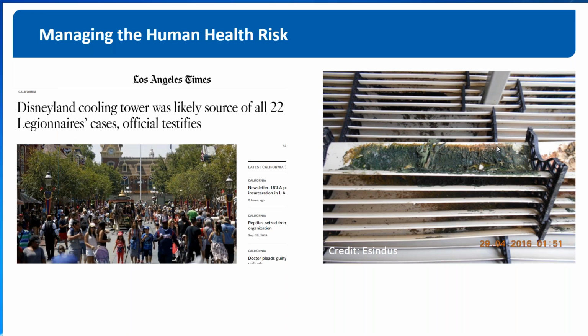Legionella bacteria grows in biofilm, which is a heat transfer inhibitor. So dispersants are normally used to keep process surfaces clean, and this process strips biofilm growth off the cooling tower structure. It's then fluidized as a suspended solid. So doses of disinfection chemicals are used to kill the bacteria, but dead zones in the cooling tower can mean that chemical dosing is ineffective.